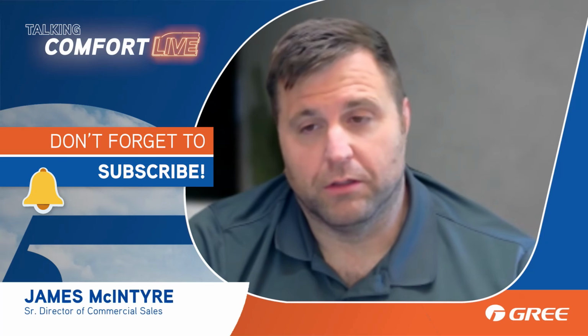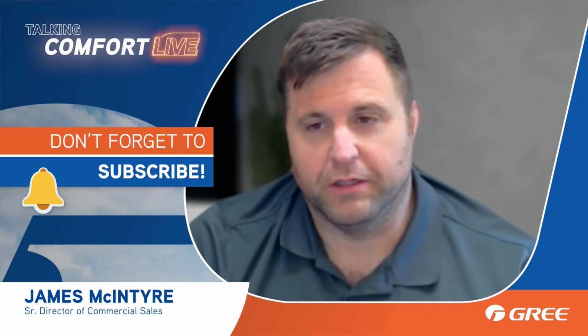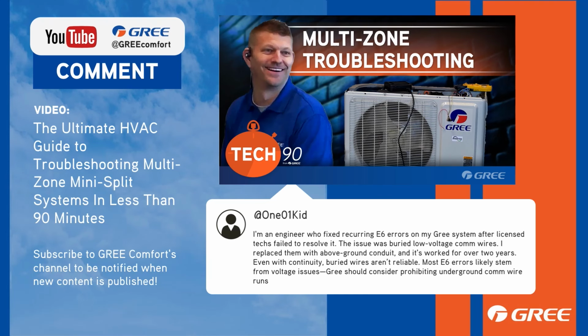But chances are, I'm going to go out on a limb and say that if part of the issue was with the communication, if they had used shielded cable and grounded that shielding at the outdoor unit only, it might have been able to bury that cable and use it as is. Anything you guys like to add on that?